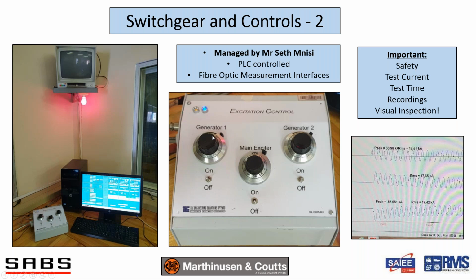This is your excitation control for generator 1 and generator 2. When you operate the two together, you have to make sure that the field current into them is approximately the same. What's important? Well, of course, safety. And I mentioned the fiber optic measurement interfaces. There's massive thick concrete walls around the test object. There's a bunker between this test facility and the offices. Then your test time and test current. So your switchgear has to be very quick and accurately controlled.